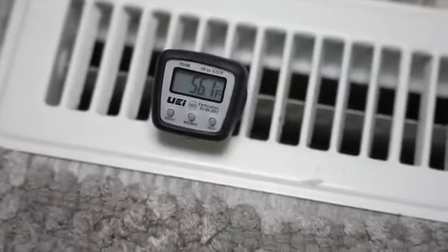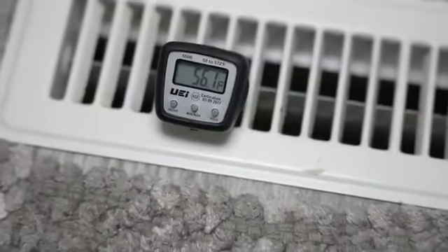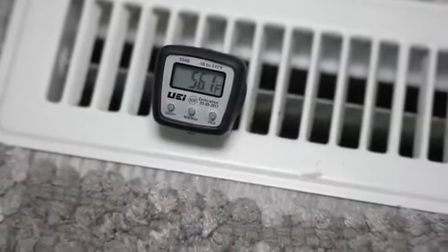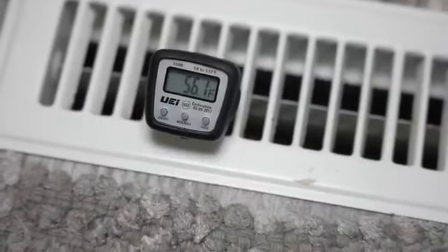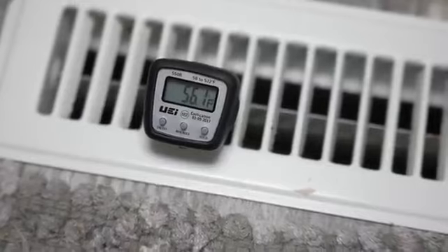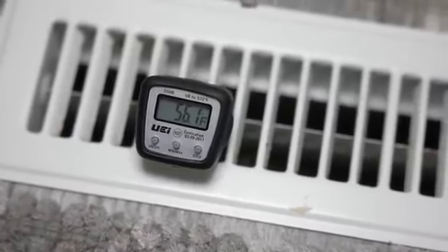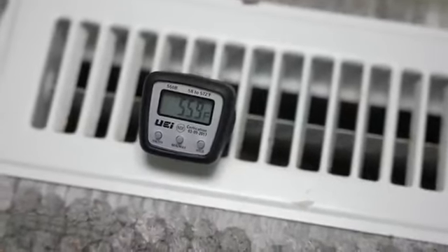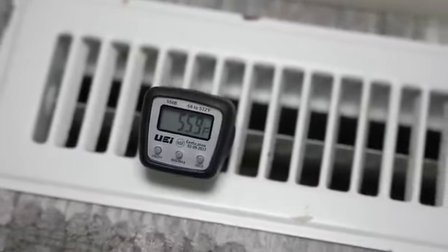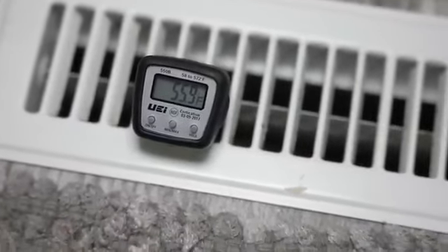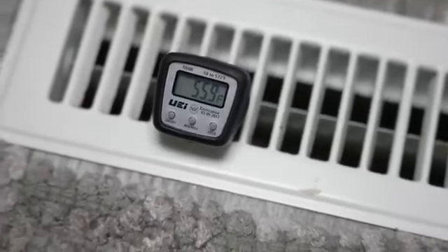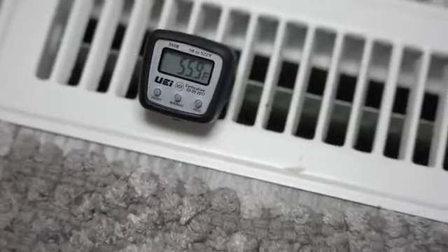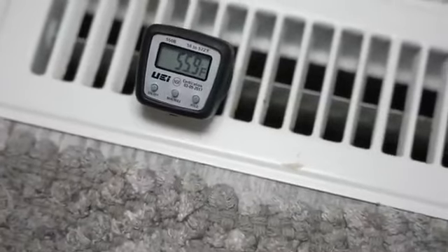And I bet you if we checked the supply ductwork down in the basement, if I were to drill a little hole there, that would probably be even a little bit lower. So as long as you're in the range of 15 to 20, that's a good sign. That means your air conditioner is working well, it's cooling well. If it's below that, let's say it's 10 degrees or even 8 degrees difference, that means there's something wrong. Either the airflow is restricted, that's why I suggested replacing the air filter, or you're low on refrigerant, and that is why it's not cooling down enough.